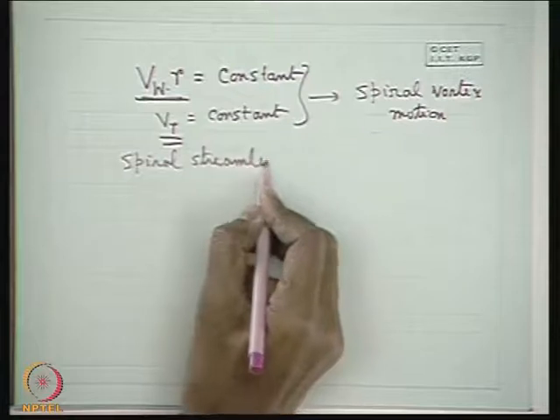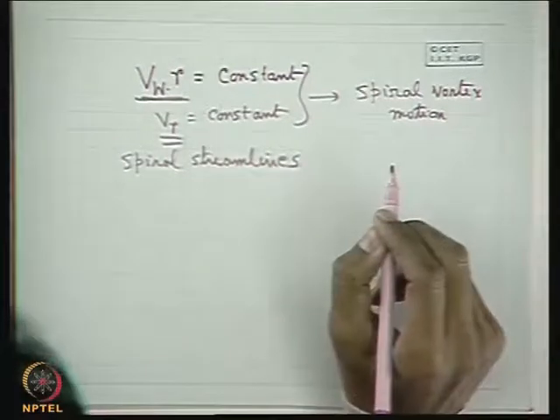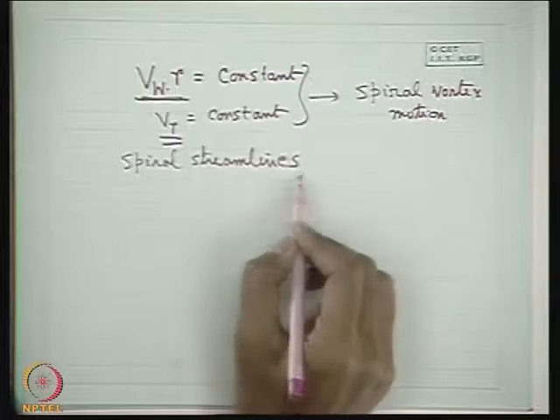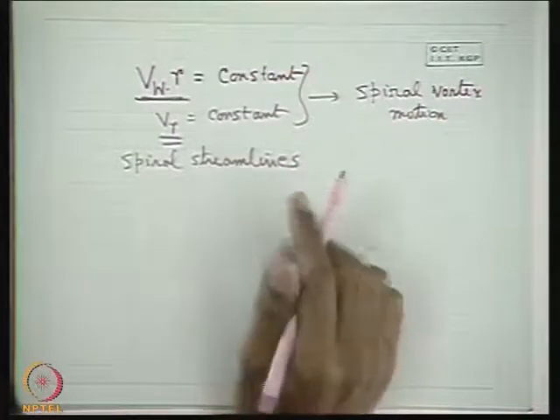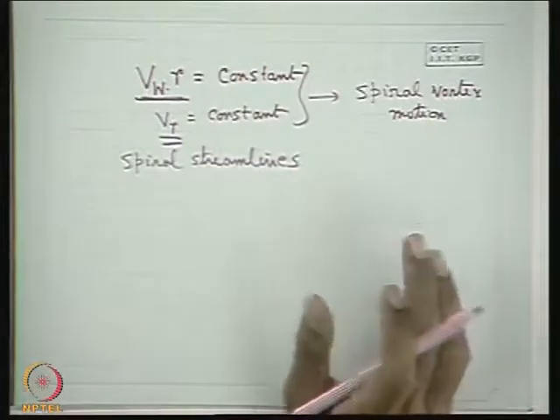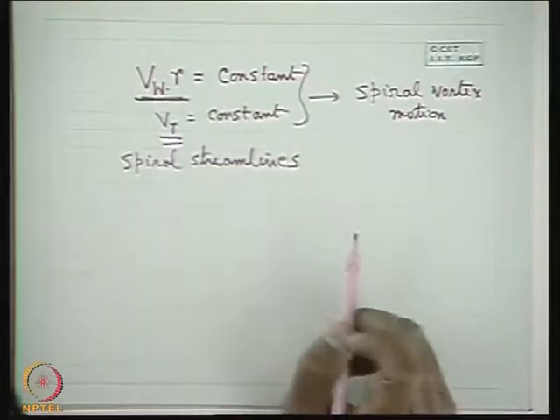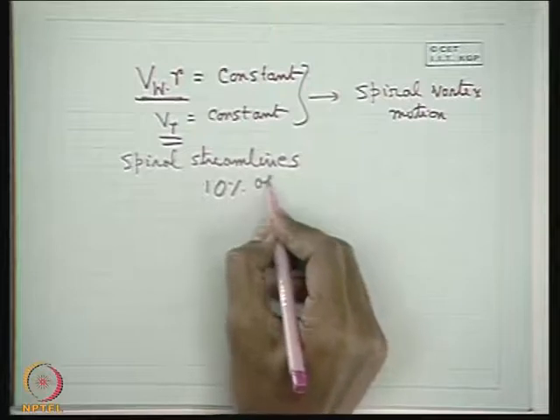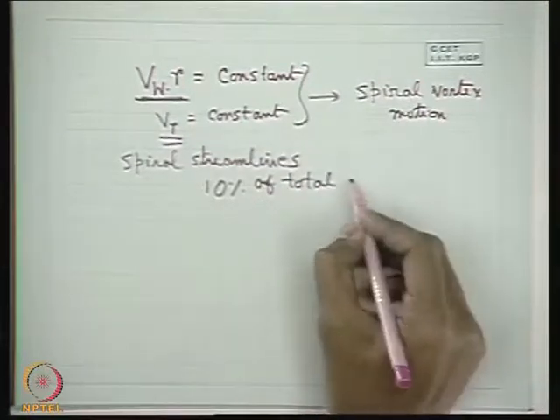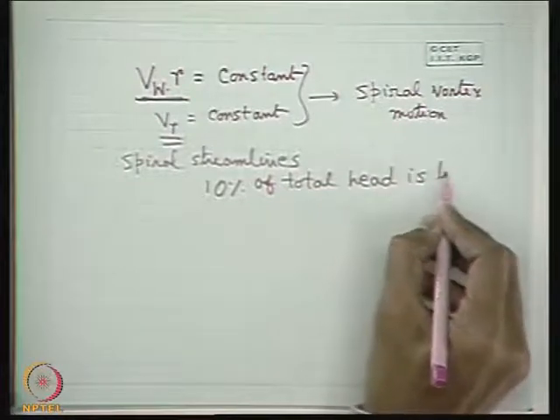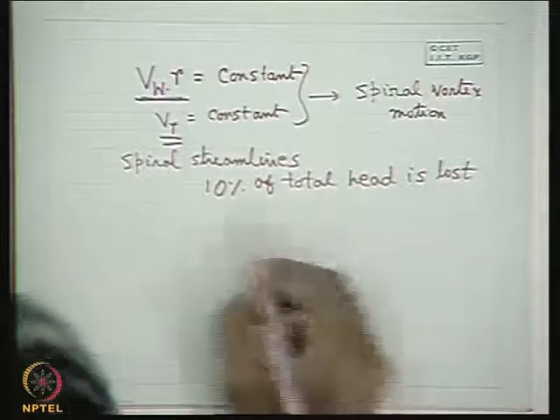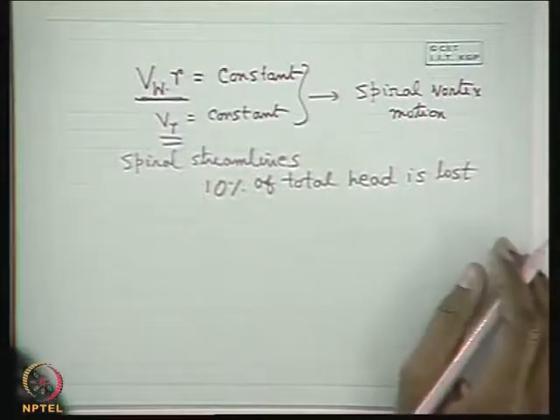The most important consideration is that the shape of the volute has to be made matching with the streamline pattern — that is, the volute must be made spiral to match the pattern of the spiral streamlines. This is one of the most important considerations in designing a diffuser. Usually, at maximum efficiency, 10 percent of the total head is lost in the diffuser due to frictional effects in converting kinetic energy into pressure energy.